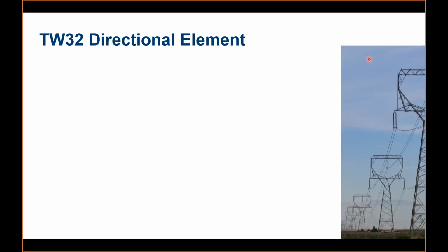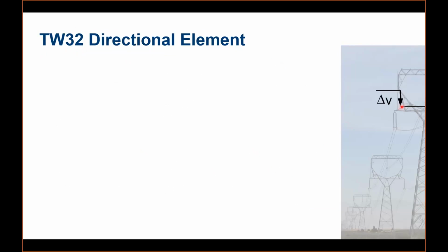Next is the element which we call a directional element, and it uses the traveling wave voltage and the current to decide the direction. These elements can be used in permissive schemes along with some other supervisory elements, which we call incremental-based directional elements. Just consider a fault over here on the right side of your screen, and you can calculate the traveling waves in the voltage and the currents with that relationship. Once they travel along the line, they will reach the station. And once they reach the station, depending on the CT polarity, the relay will detect the traveling waves in the voltage and the current in a negative direction if the fault is in the forward direction.